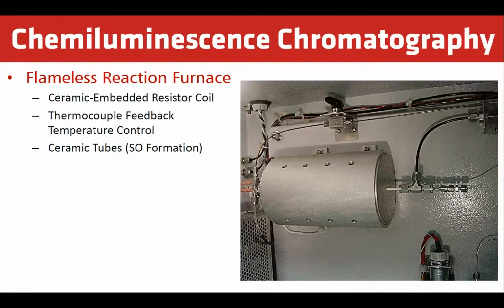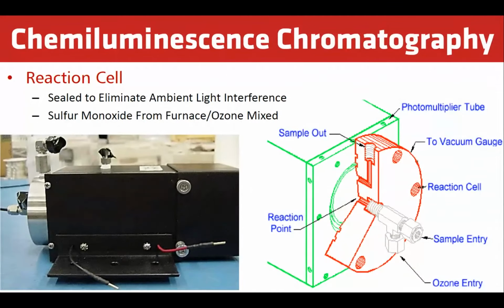So basically, after the sulfurs are separated in the column in the previous slides, we come down and we add combustion air to the separated sulfur, and then into the ceramic tubes where we add hydrogen to do the reduction to SO. Part of the chemiluminescence reaction cell, this reaction cell is sealed to eliminate ambient light interference. Sulfur monoxide forms in the furnace and is mixed with ozone. So basically what you're looking at is SO after it comes out of the oxidation reduction oven.